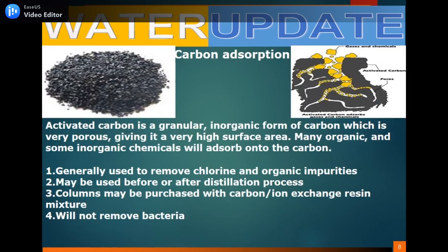The next method is carbon adsorption. Activated carbon is a granular, inorganic form of carbon which is very porous, giving it a very high surface area. Many organic and some inorganic chemicals will adsorb onto the carbon. It is generally used to remove chlorine and organic impurities, and may be used before or after the distillation process. Carbon may also be purchased as a mixture with ion exchange resin. It will not remove bacteria.